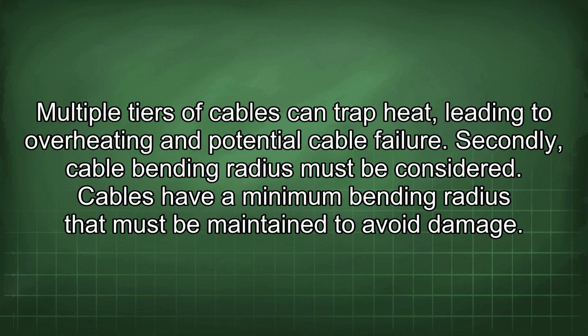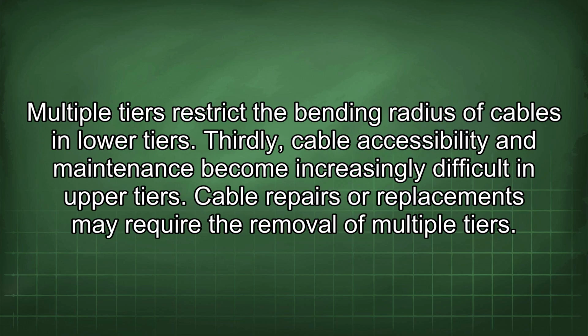Secondly, cable bending radius must be considered. Cables have a minimum bending radius that must be maintained to avoid damage. Multiple tiers restrict the bending radius of cables in lower tiers. Thirdly, cable accessibility and maintenance become increasingly difficult in upper tiers. Cable repairs or replacements may require the removal of multiple tiers.